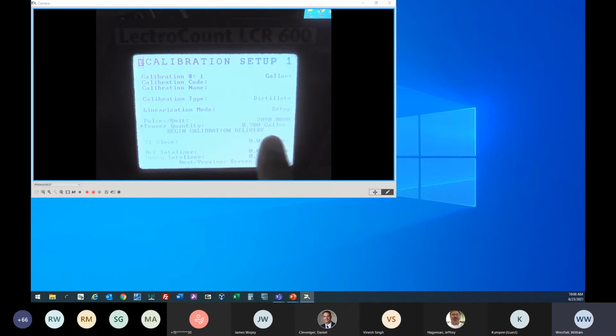Now, if you noticed, our pulses per unit actually changed on its own. We didn't have to do any kind of calculations or anything like that. Once you enter in the prover quantity, it will adjust your pulses per unit for you. In this case, this is in gallons, so we're looking at 2,090 pulses per gallon.